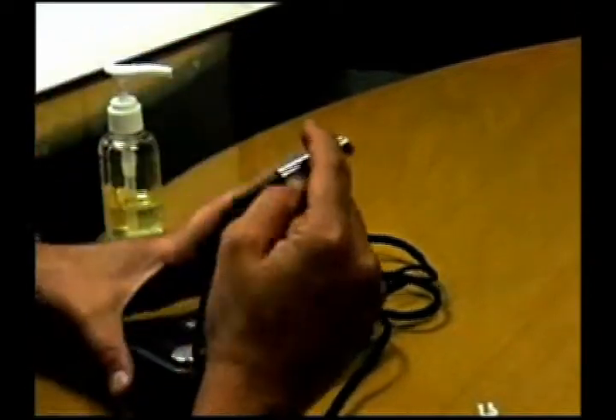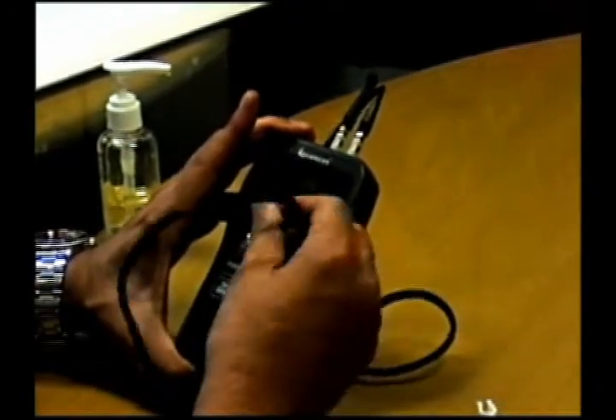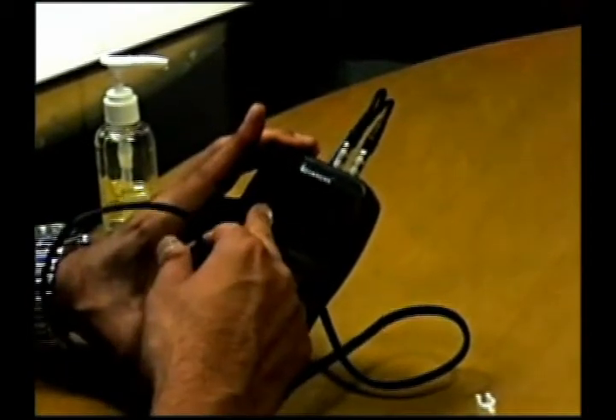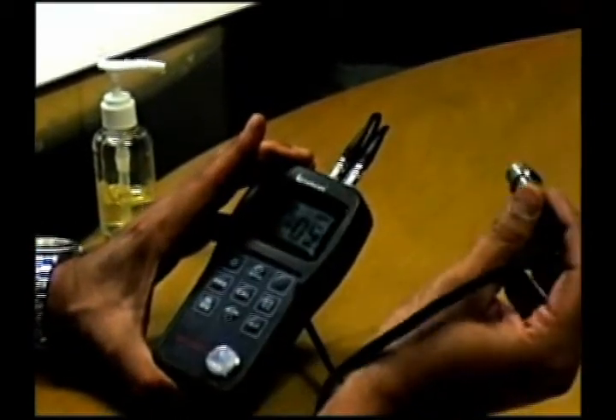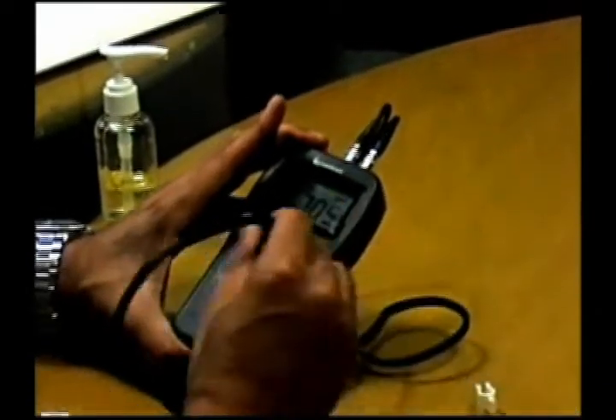Now, before we start using the transducer, we press the PRB button over here, which means a probe zero. That means we are first calibrating the transducer itself. At the moment we press the PRB button, it displays P05, which means that the transducer that we are using is a P05 transducer, which is operating at 5 MHz frequency.